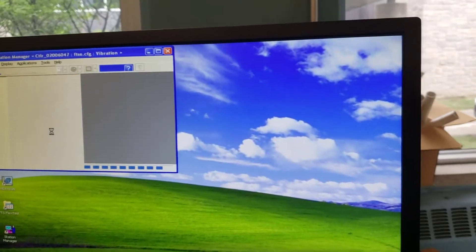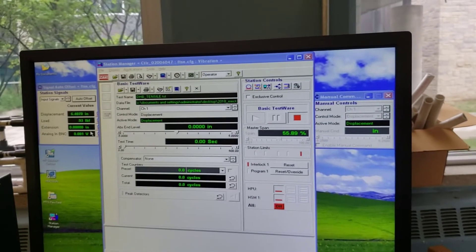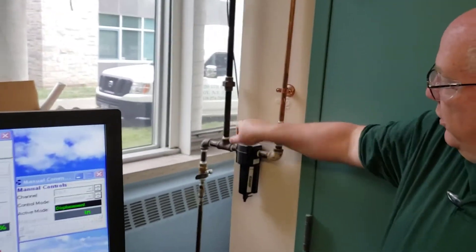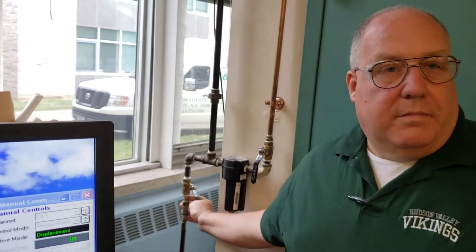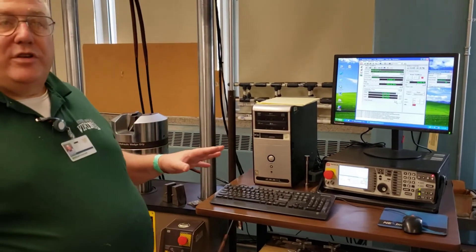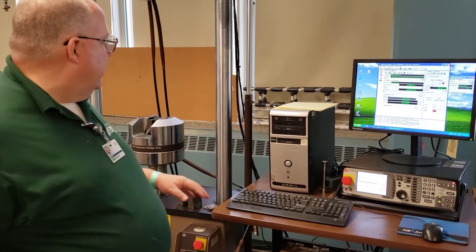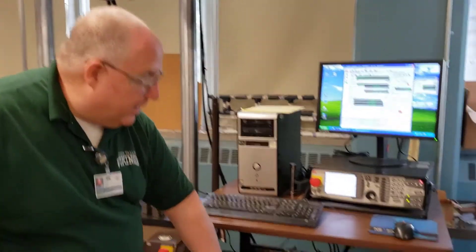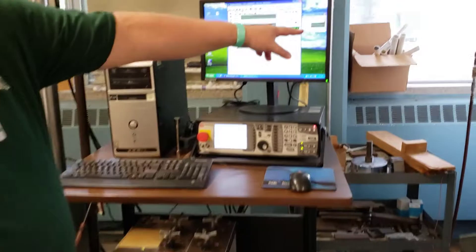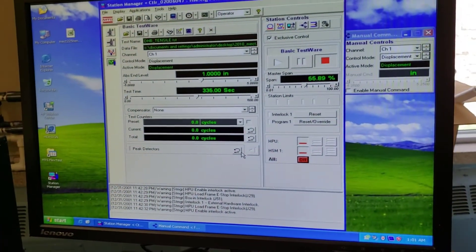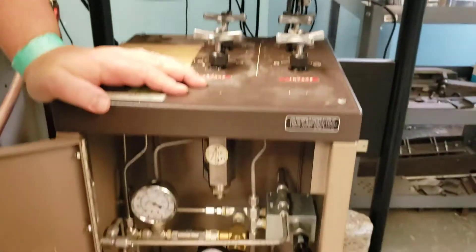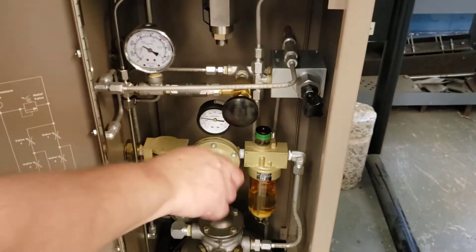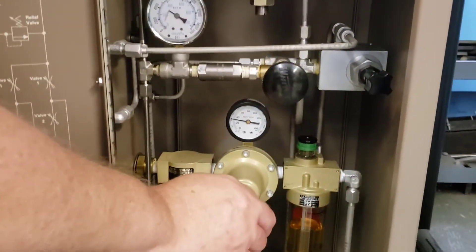Now, I want to power up the rest of the system. You'll notice everything is off. We turn the air on to the system and then we can crank that up. Now that the machine is up and powered, we can set the pressure for the grips. That's done under here. The air is on and you'll notice both of my valves are in the on position for the air. Then I can come underneath here, using this knob, set it to about between 20 and 40 pounds.